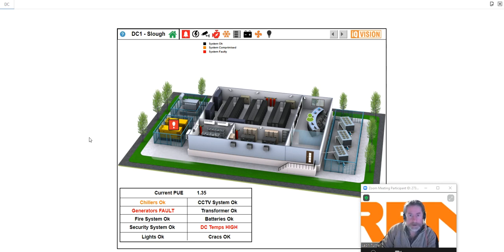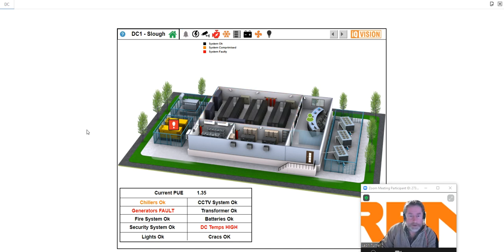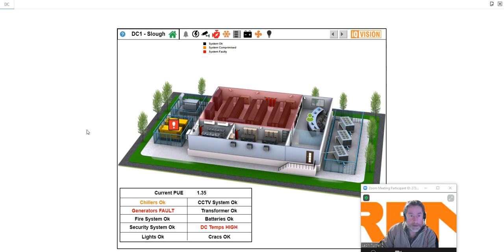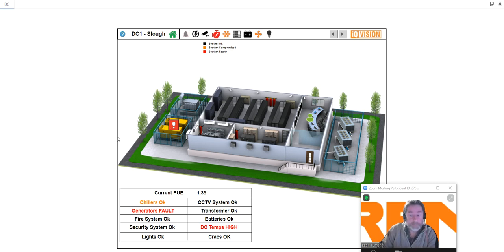What we're trying to present here is the idea that the supervisor for a data center doesn't have to be complicated and can be done in a very simple fashion. What we have really tried to lean on here is something which we refer to as supervision by exception. This means presenting the operator with very little information, but only things they absolutely have to know are made obvious. On the screen in front of you, you can see that most of the colors are quite muted. There isn't an awful lot of data splashed all over the place.